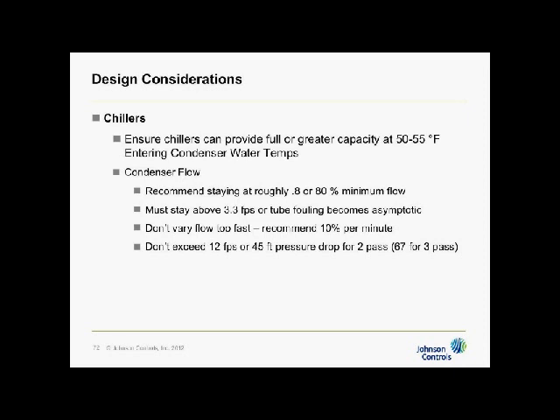Don't vary the flow too fast. Again, we recommend 10% per minute. There's no reason to, and going too fast can often give some instabilities. Don't exceed 12 feet per second or 45-foot pressure drop roughly for our 2-pass chiller. You can go a little bit higher, 67 feet for a 3-pass. Again, for the same considerations on chill water flow, you have the same limits on condenser water flow.